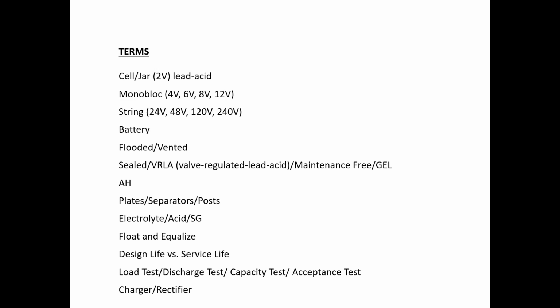It's kind of important when you look at European batteries. It's not apples to apples. They usually use a 5-hour rate. So that's really more of a sizing issue, not so much a maintenance issue, but it's something to keep in mind as we're talking. Plate separators and posts, we'll look at those.